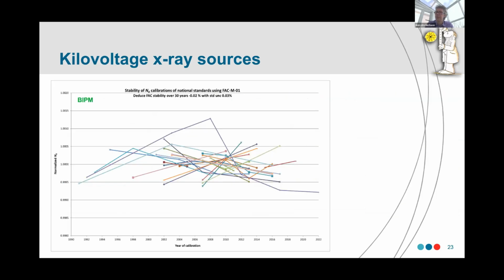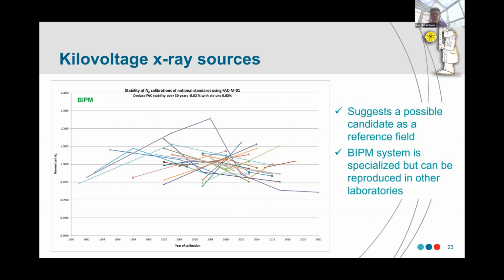So this is the data that David Burns at the BIPM supplied. These are calibrations using their free air chamber and multiple detectors, and as you see, the vast amount of that data sits within plus or minus 0.05%. And that suggests 0.05% is probably sufficient for long-term metrology. We'd like it to be better, and if we look at cobalt-60 data, we can certainly get better than that over longer periods because of the predictability of source decay.